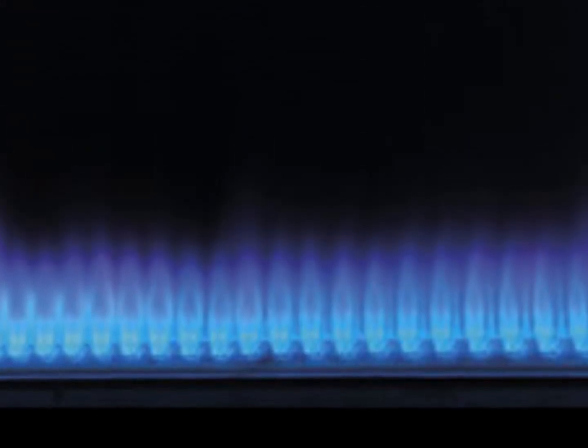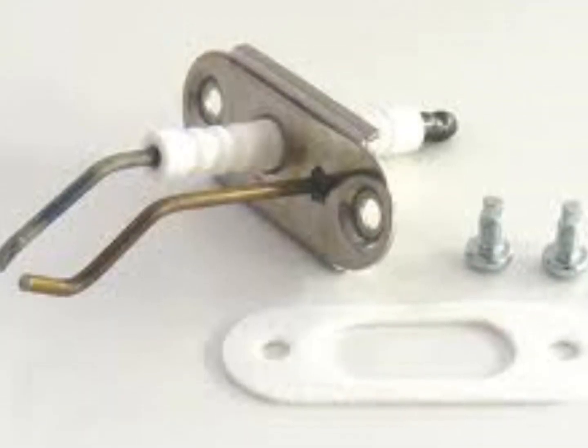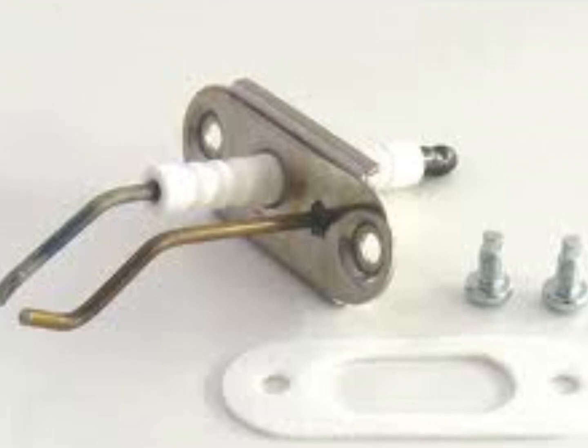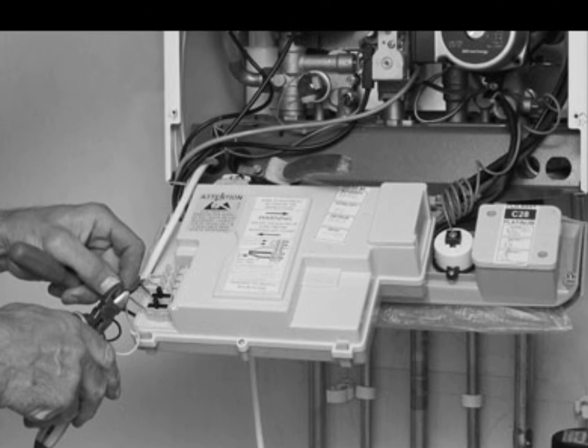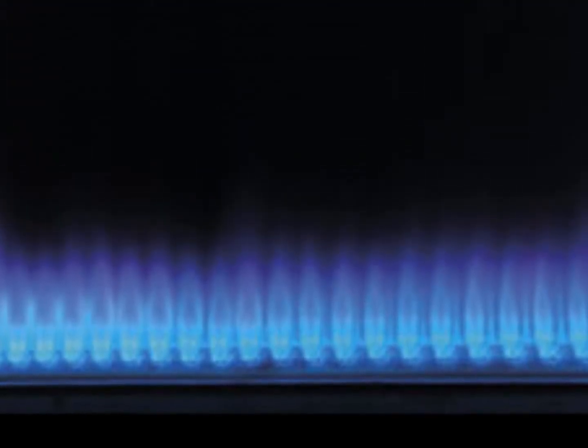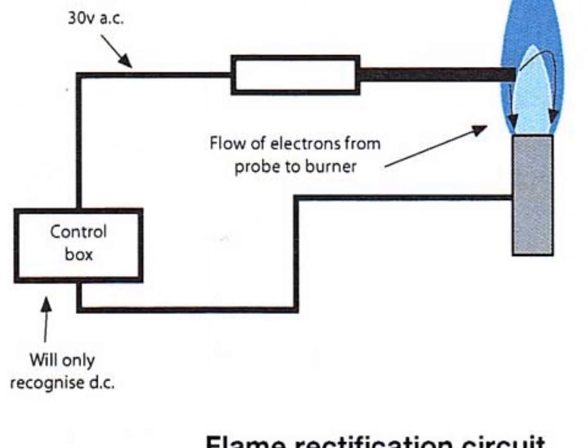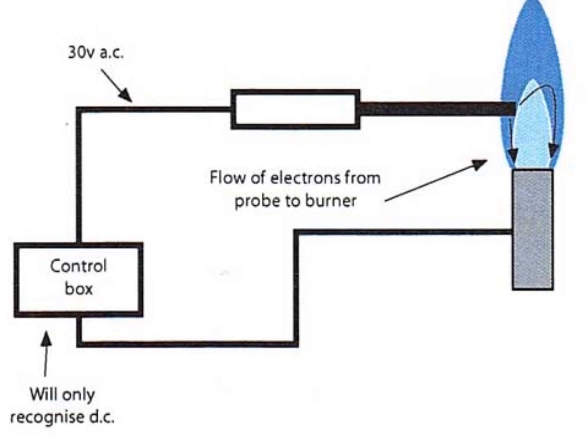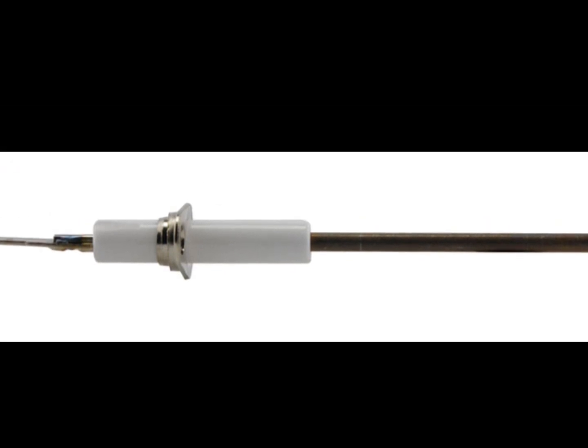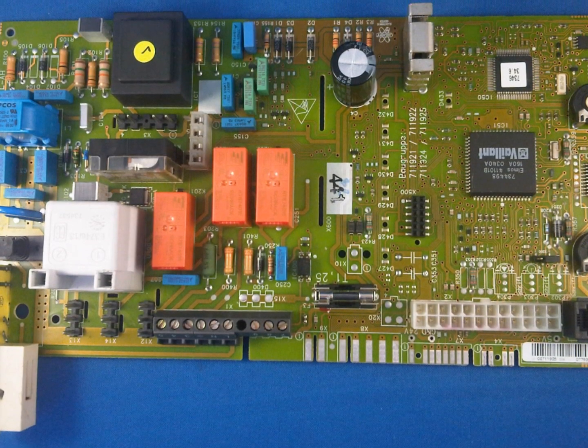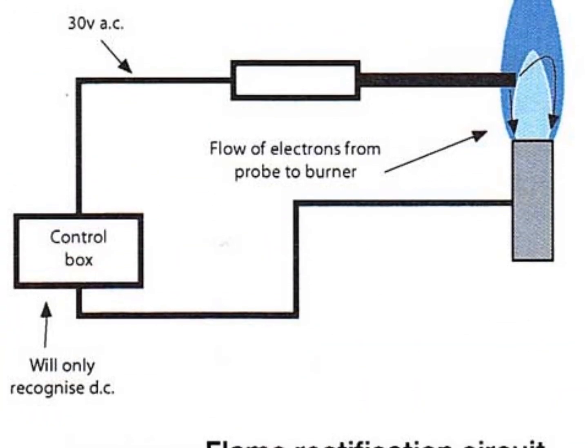There's then an ignition probe, like a spark plug, which starts trying to light. Once that lights it, you've got a flame. Once the flame occurs, you've got another device called a flame rectification device — essentially just a probe. When the flame hits it, it generates a small current which goes back to the PCB, telling the PCB to keep the gas valve open. If it's not detecting any current, it's going to shut off, because we don't want the boiler filling up with gas.